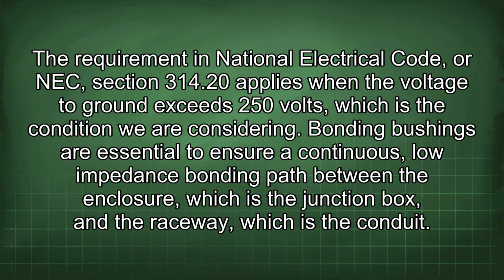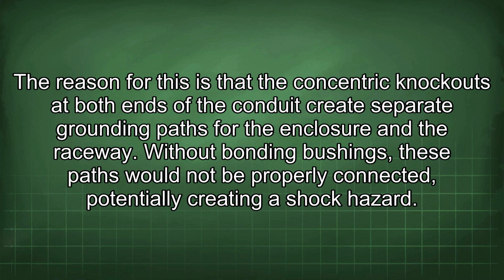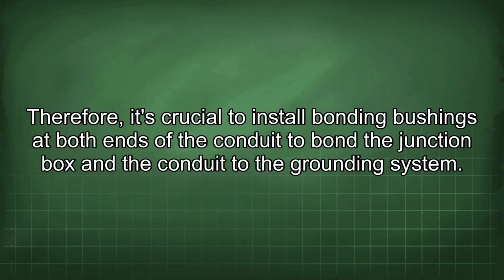Bonding bushings are essential to ensure a continuous, low-impedance bonding path between the enclosure, which is the junction box, and the raceway, which is the conduit. The reason for this is that the concentric knockouts at both ends of the conduit create separate grounding paths for the enclosure and the raceway. Without bonding bushings, these paths would not be properly connected, potentially creating a shock hazard. Therefore, it's crucial to install bonding bushings at both ends of the conduit to bond the junction box and the conduit to the grounding system.